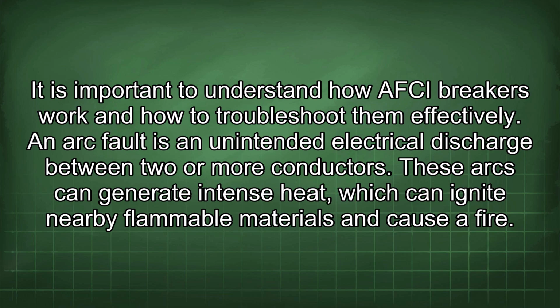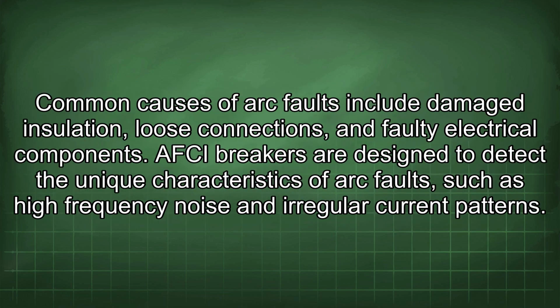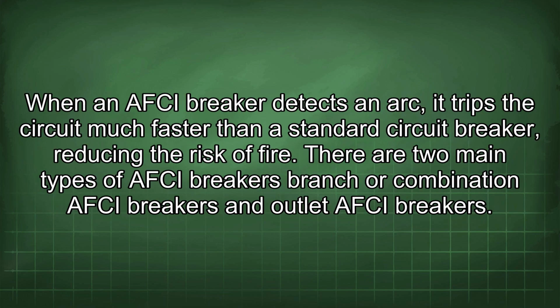An arc fault is an unintended electrical discharge between two or more conductors. These arcs can generate intense heat, which can ignite nearby flammable materials and cause a fire. Common causes of arc faults include damaged insulation, loose connections, and faulty electrical components. AFCI breakers are designed to detect the unique characteristics of arc faults, such as high-frequency noise and irregular current patterns. When an AFCI breaker detects an arc, it trips the circuit much faster than a standard circuit breaker, reducing the risk of fire. There are two main types of AFCI breakers: branch or combination AFCI breakers and outlet AFCI breakers.